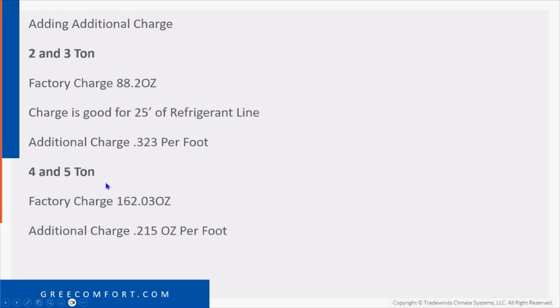4 and 5 ton, a lot more charge in that unit. We've got 162.03 ounces. And the additional charge is 0.215 ounces per foot.